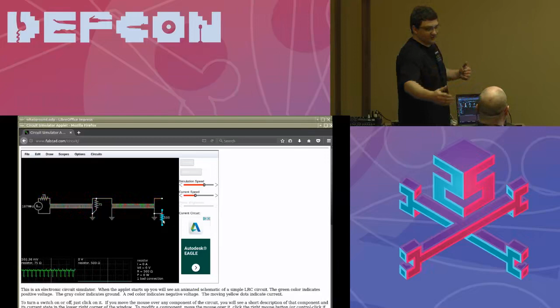If there's an impedance mismatch at the ends of the line, the signals start bouncing off the end, producing a very noisy signal. This is why you always need to terminate these buses, or have some self-termination, because the impedance needs to appear to continue on to infinity—it makes the wire look like it's infinitely long.